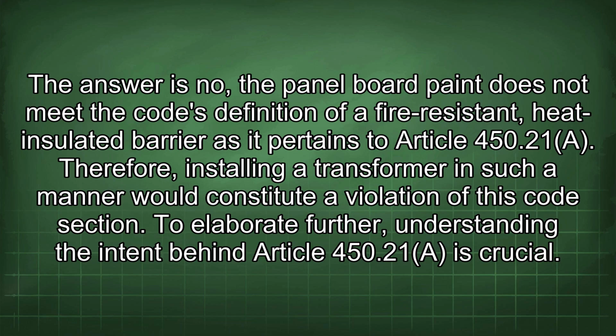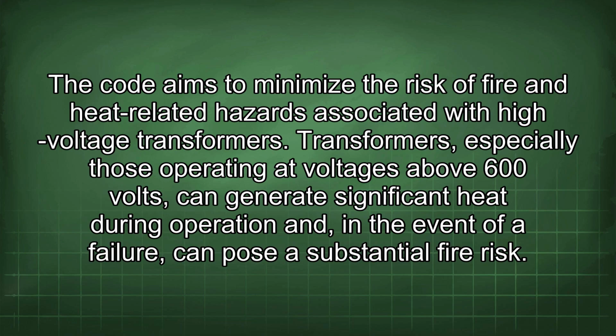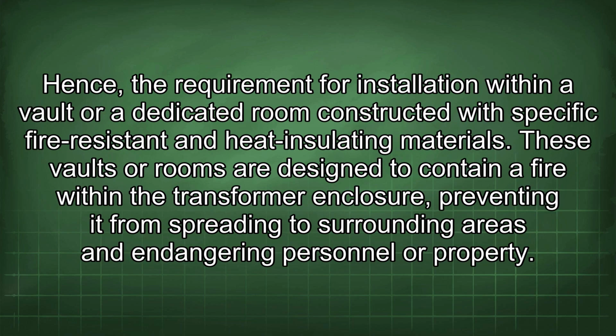To elaborate further, understanding the intent behind Article 450.21 is crucial. The code aims to minimize the risk of fire and heat-related hazards associated with high-voltage transformers. Transformers, especially those operating at voltages above 600 volts, can generate significant heat during operation and, in the event of a failure, can pose a substantial fire risk. Hence, the requirement for installation within a vault or a dedicated room constructed with specific fire-resistant and heat-insulating materials. These vaults or rooms are designed to contain a fire within the transformer enclosure, preventing it from spreading to surrounding areas and endangering personnel or property.